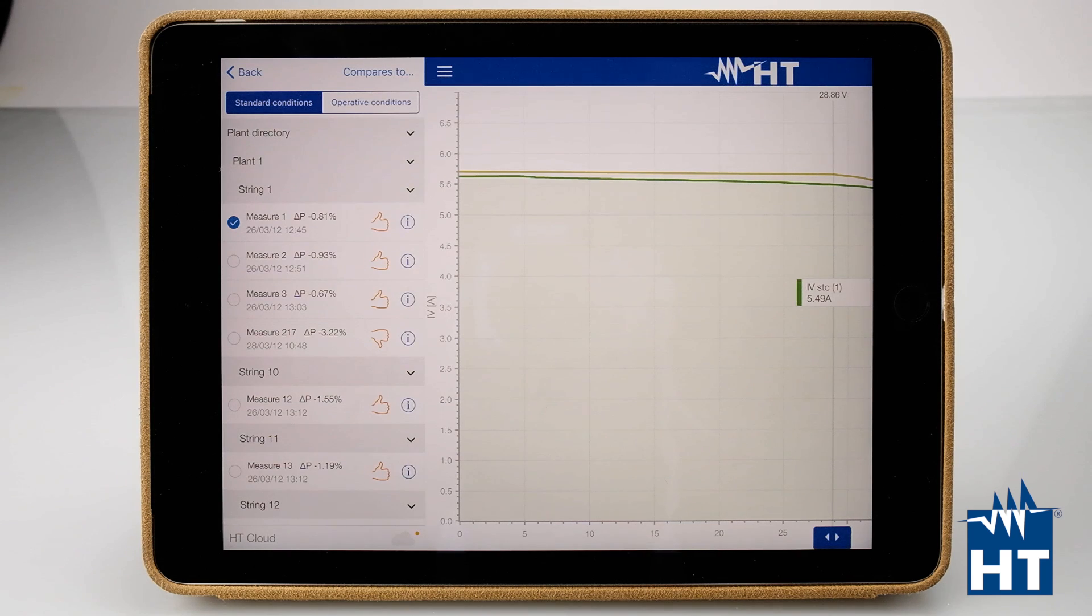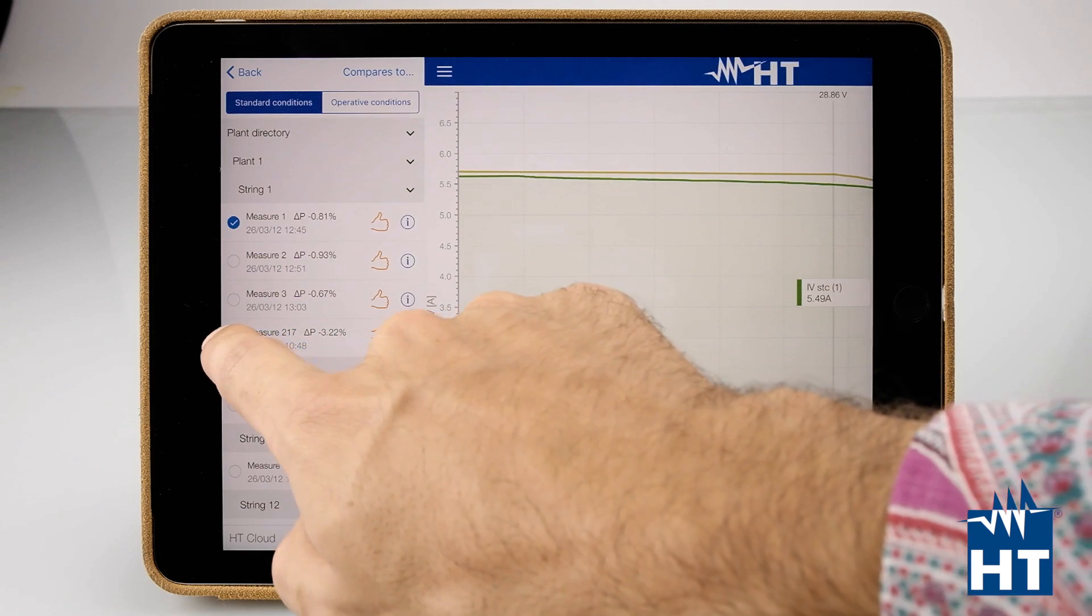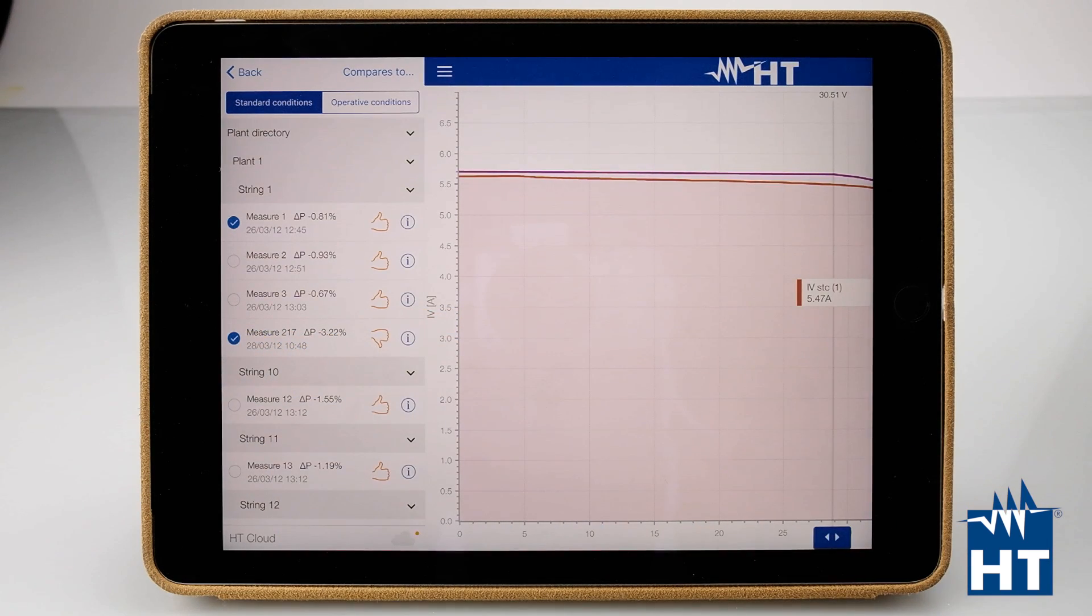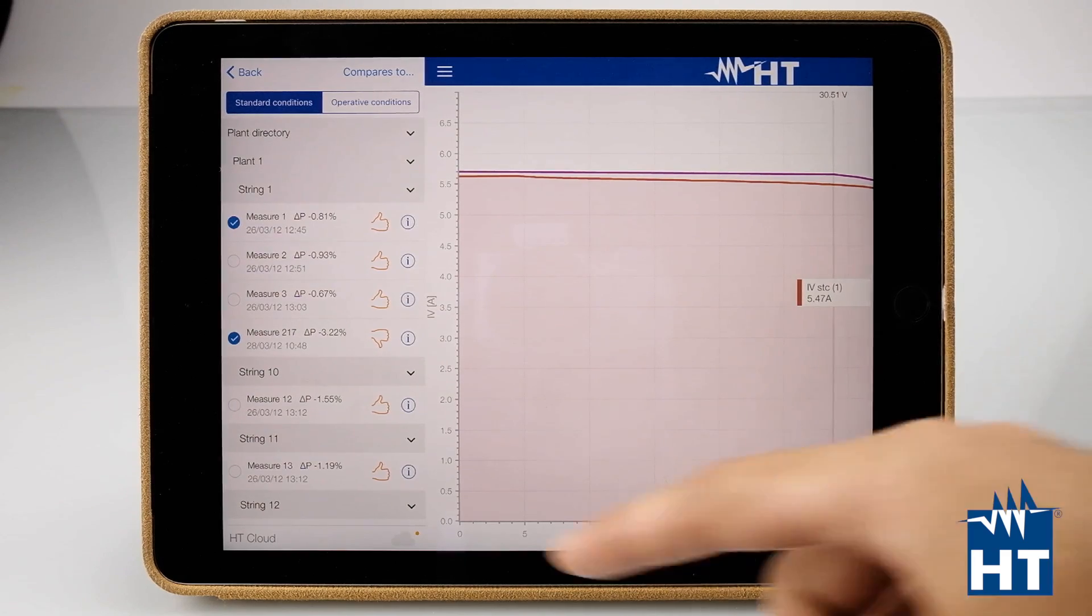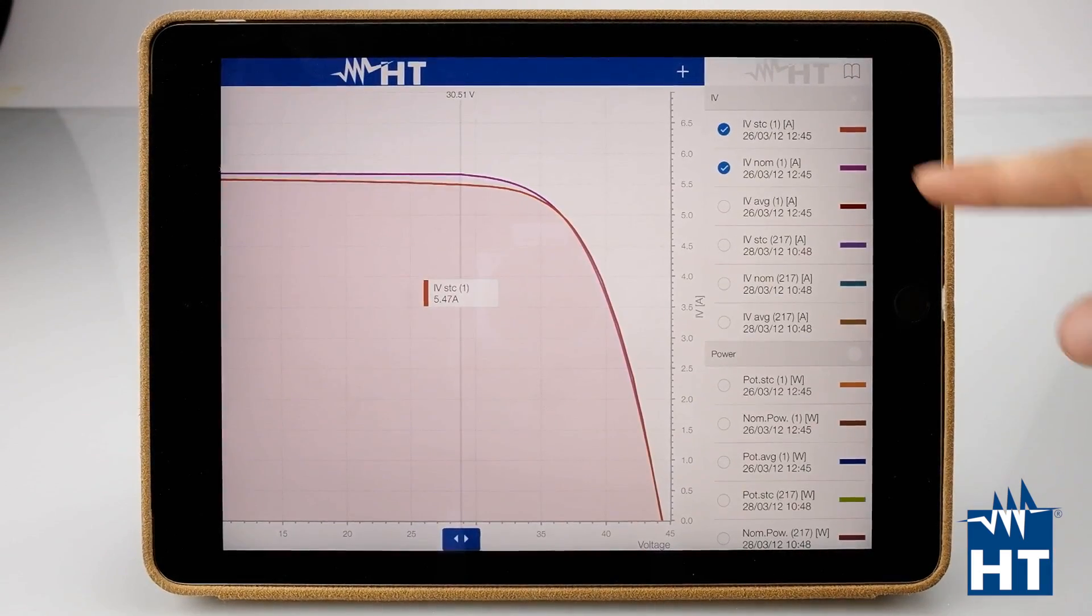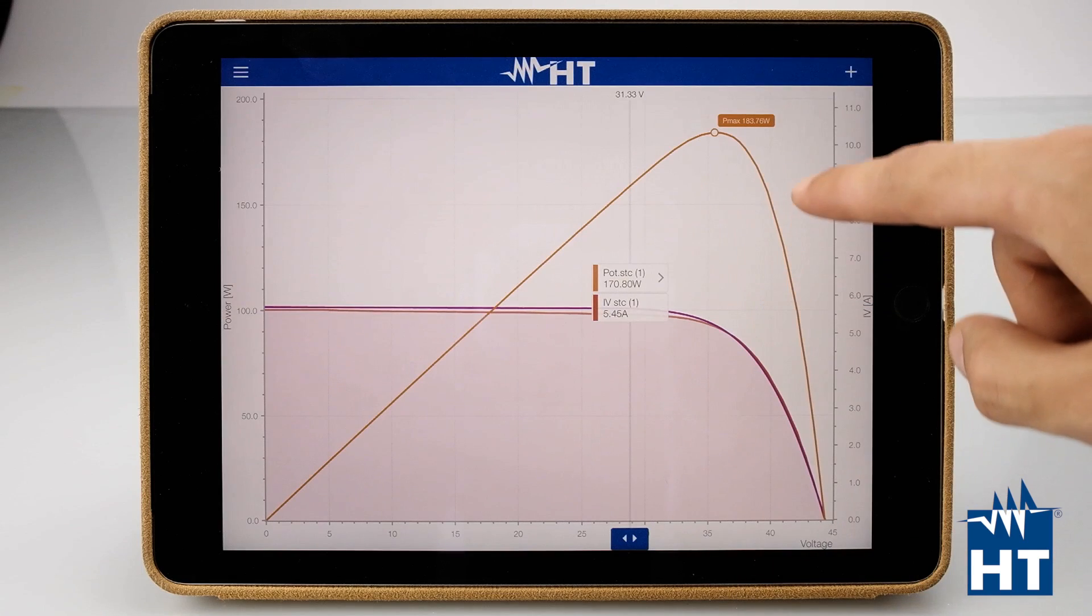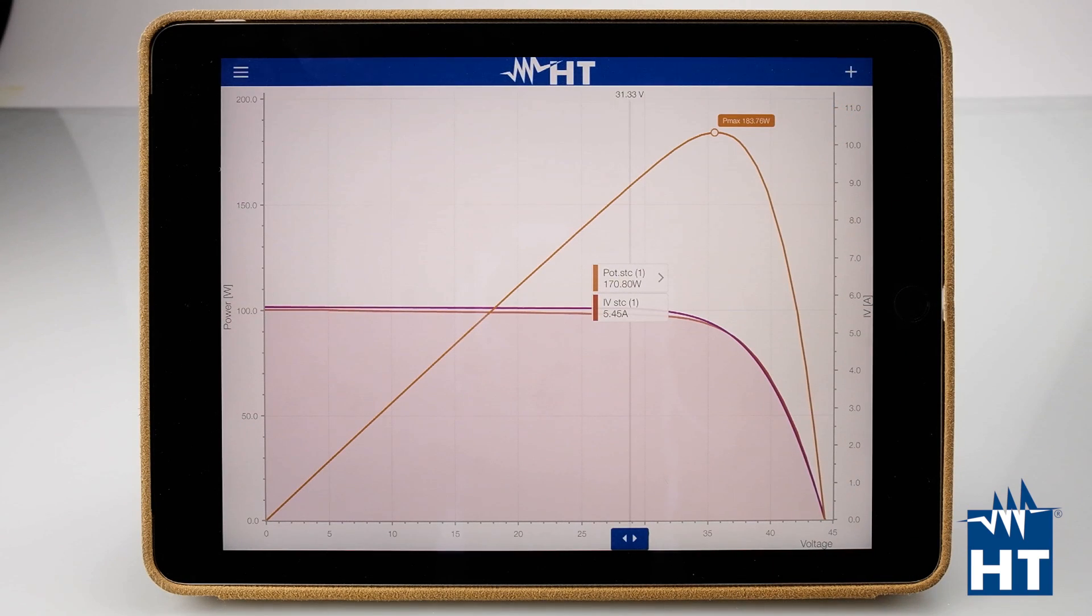The other important part is that you can compare the measurements from two different periods. I've done these measurements today and I've done this one two weeks ago or two months ago. Now I have two measurements on the same graph and I can compare also the power. For example, power STC with the maximum power point here and then you have now the complete data to say something about, this module is not okay or maybe this string is not okay or this plant needs more maintenance or let's just clean the panels.